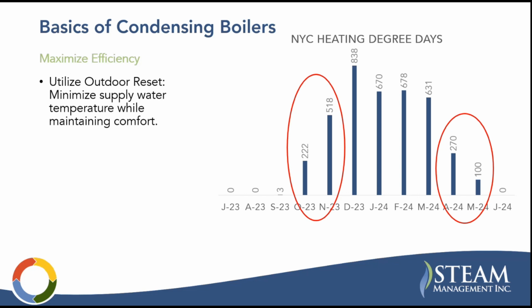This is a plot of heating degree days in New York City. When you're really going to get this condensing mode is on these shoulder months where you have somewhat milder temperatures. You can reduce that set point and get the full efficiency out of the boiler.